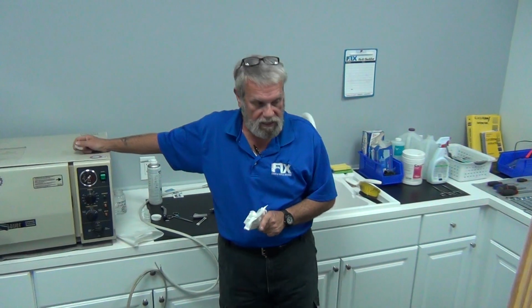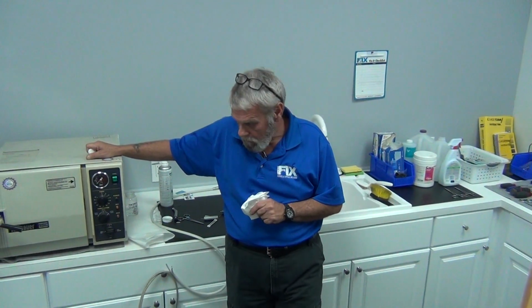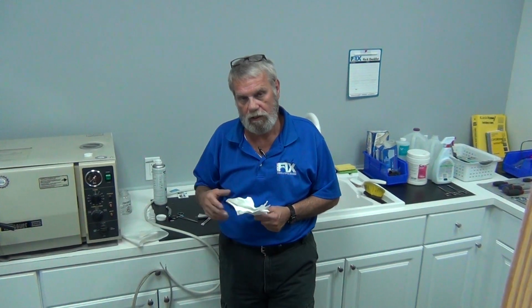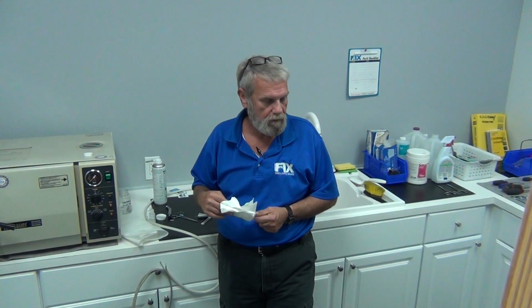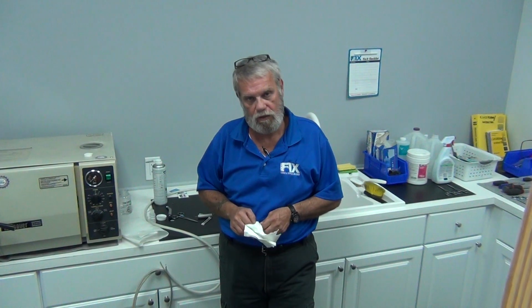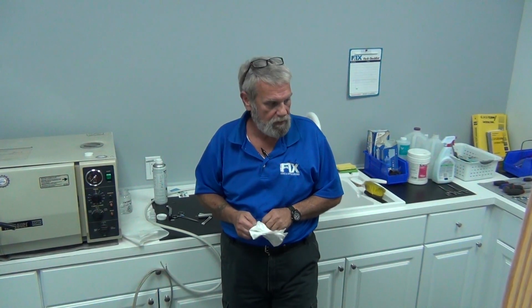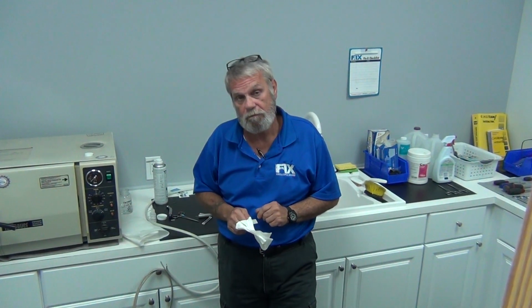let's talk a minute about the drying cycle again. I reiterate, make sure that plastic's down and the paper's up, because the steam will actually rise out of the paper and help dry the handpiece better. You want that handpiece as dry as possible. You also want that handpiece cycle to go as quickly as possible. The less that handpiece is exposed to 270, the longer that handpiece will last. But it has to be exposed to 270 for efficient sterilization. But it only has to be exposed at 270 degrees for 4 minutes.